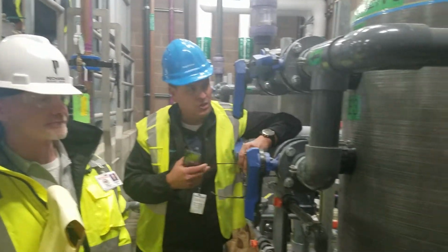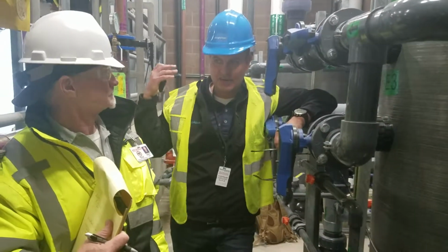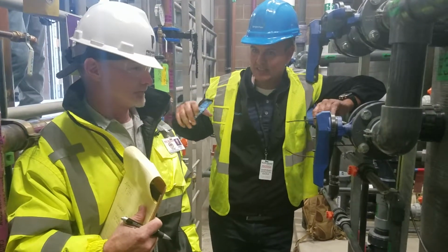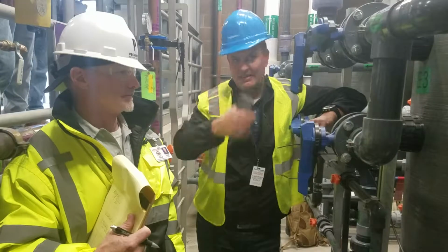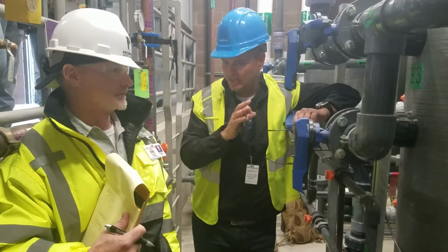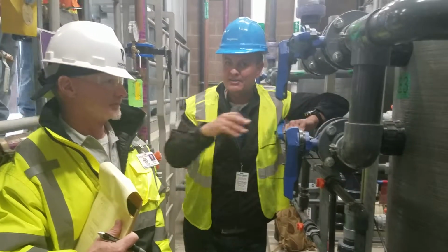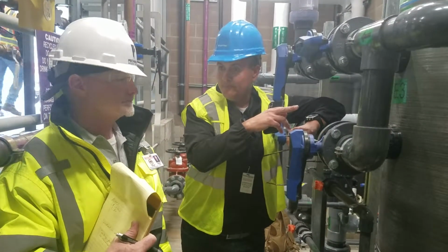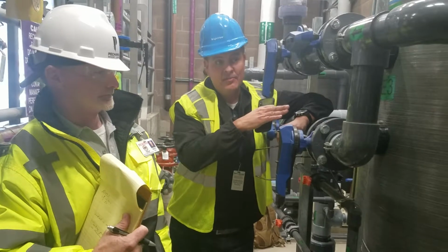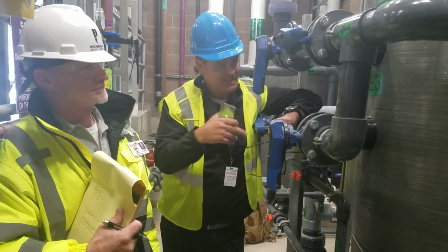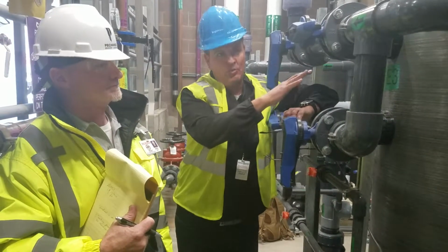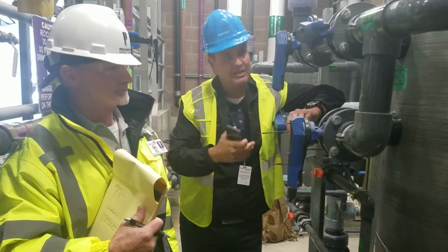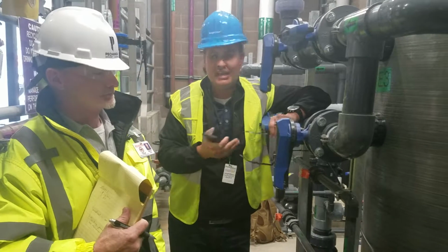Correct. Because once we get these controllers set, once our ambient temperatures are stabilized, so we get into a summer and our ambients are fairly consistent, controllers don't need to be worked with and calibrated constantly. They find a balance, and there are adjustments that we make in the probe systems and the way they read. So the more consistent we keep the flow, the more consistent the readings, the more consistent our water is, the more consistent our chemical usage becomes. So that's what we're looking for.